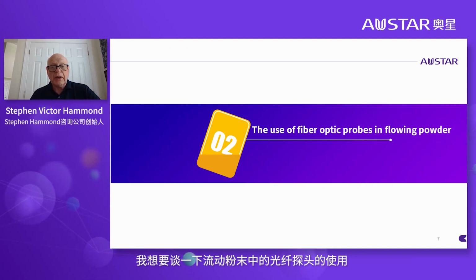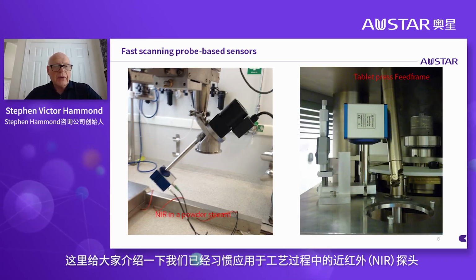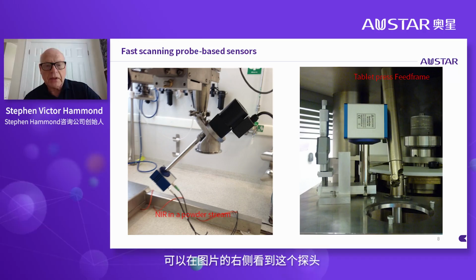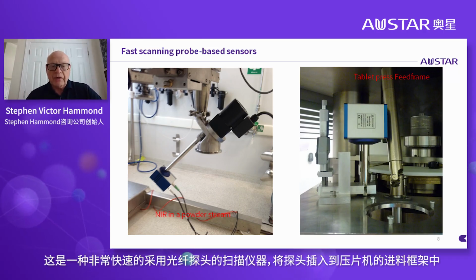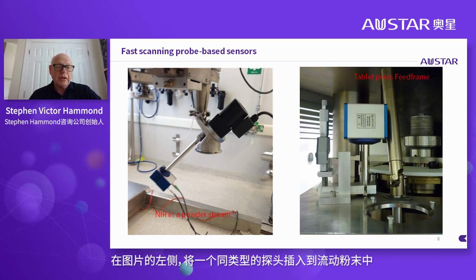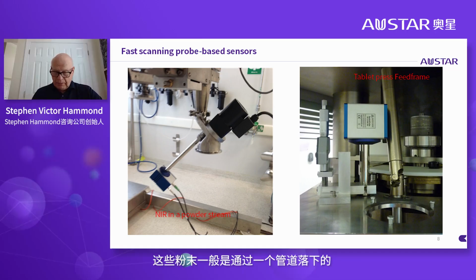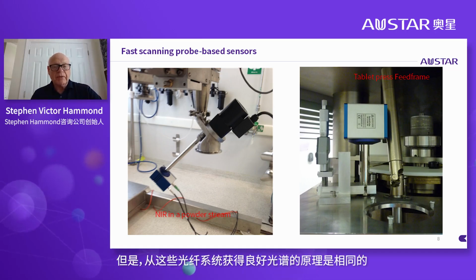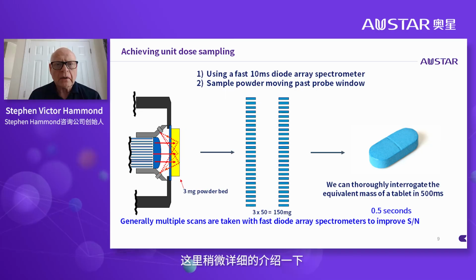So I want to talk a little bit about fiber optic probes in a flowing powder. So here I'm going to show the near infrared probe that we've tended to use inserted into the process. And on the right-hand side you can see the probe. It's a very fast scanning instrument that uses fiber optic probes, and the probe is inserted here into the feed frame of the tablet press. And on the left-hand side the same type of probe is inserted into flowing powders, just generally moving down a pipe. But the mechanism for getting good spectra from these fiber optic systems is the same. And I do want to talk in a little bit of detail about them.